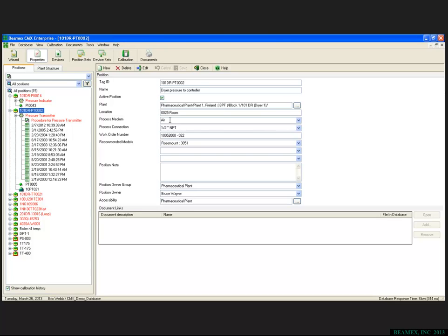It tells you that the process medium is air, that it's connected by a 1/2-inch MPT connector, and this is the work order number for that particular asset when it was calibrated. There are recommendations for model numbers, Rosemount 3051, for example, and then you get a little more information with regards to where it's owned, and you can place notes for this particular position if that's what you need to do.